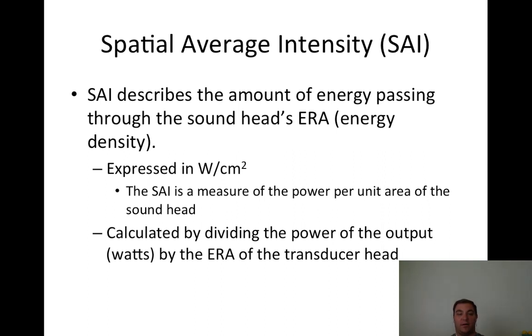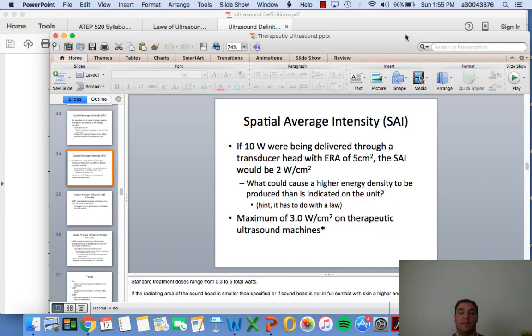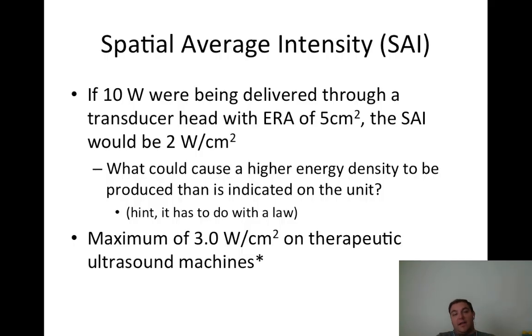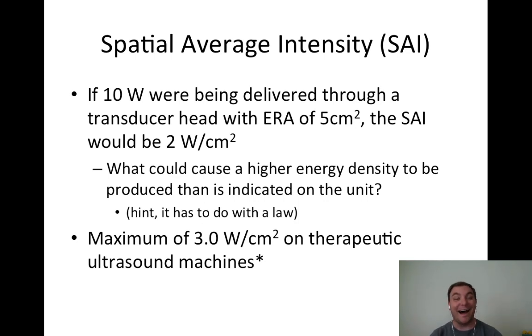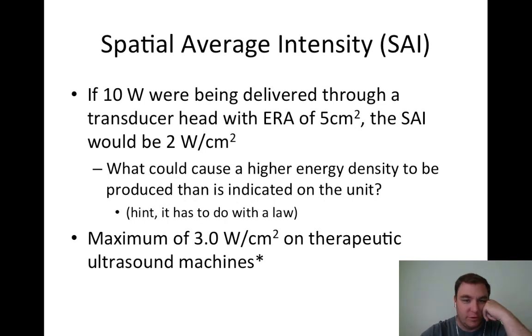SAI is calculated by dividing power output by the ERA of the transducer head. For example, if 10 watts were being delivered through a transducer with an ERA of 5 centimeters squared, the SAI would be 2 watts per centimeter squared. Standard treatment doses range from 0.3 to 5 total watts.